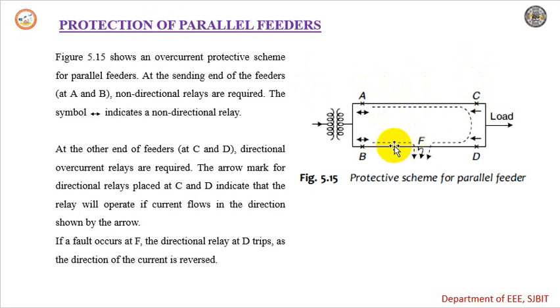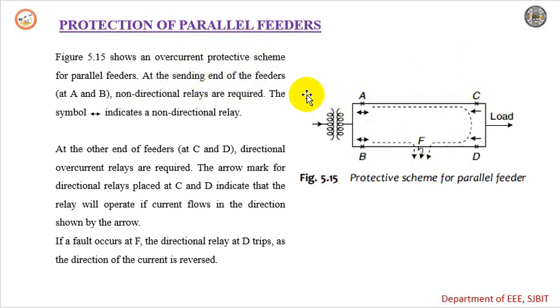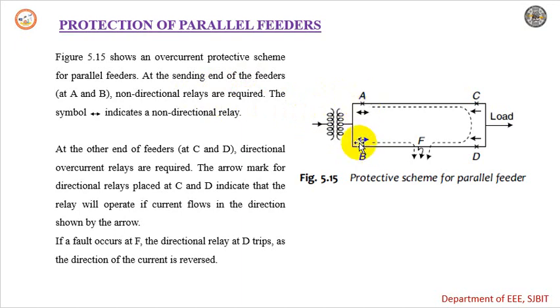This is the protective scheme used for parallel feeders. Here we have two parallel feeders. The overcurrent protective scheme for the parallel feeders is shown in this figure. At the sending end of the feeder, that is at A and B locations, non-directional relays are required. The non-directional relays are represented by the double-sided arrow symbol. Both A and B are non-directional.